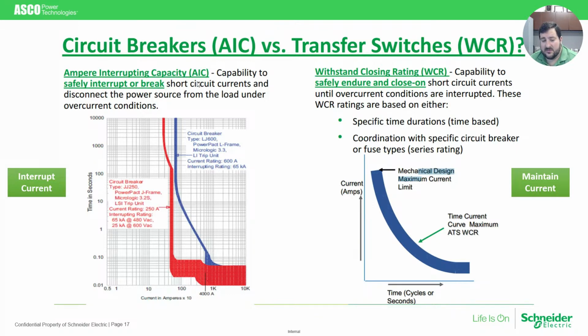A transfer switch is different. A transfer switch is not meant to provide protection against fault. It's meant to provide power resiliency, to transfer and manage power between your sources. Its real intention when it comes to fault scenarios is to withstand and survive the fault. And that's where WCR comes from, and that stands for withstand and closing rating. So that really means that if there is a fault on your electrical system, the transfer switch must be able to endure the fault for the duration of time that it takes the circuit breaker to clear the fault and still be able to operate effectively and safely afterwards.